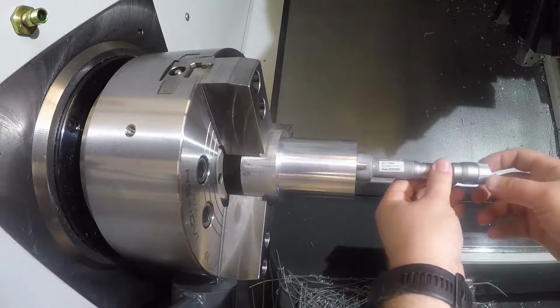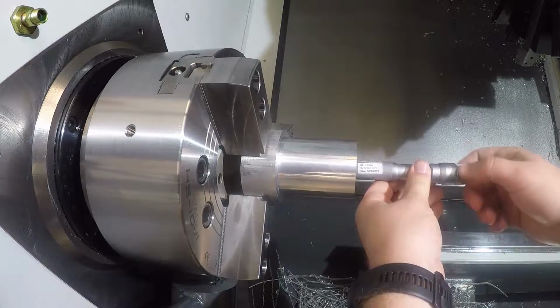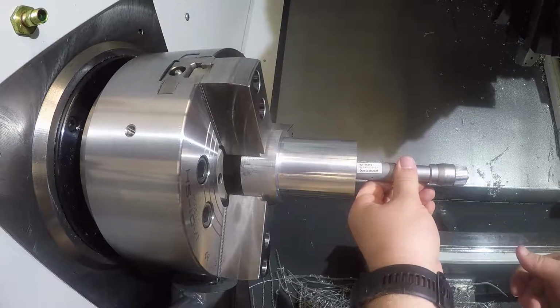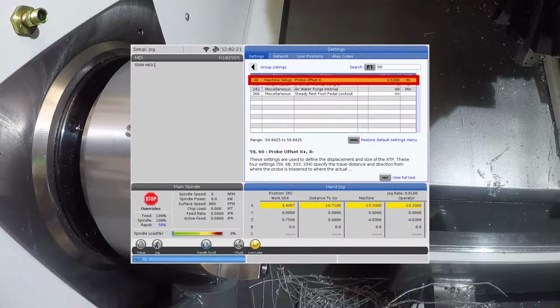I programmed an ID of 1.5, but the part came out with an ID of 1.503, a difference of 3 thou. Therefore, I will adjust setting 60 by 3 thou. If the part came out 3 thou too small, we would subtract 3 thou from setting 60. Update macro variable 10583 with the new setting 60 value. Your ATP is now calibrated and ready to use.